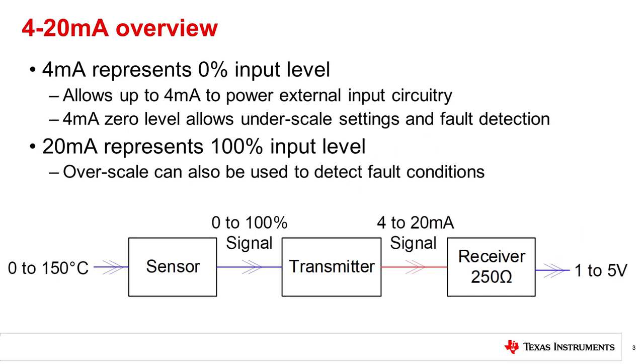The 4 to 20 milliamp current loop was designed to emulate the old 3 to 15 psi pneumatic system that was used up until the 1950s to facilitate industrial controls throughout a building. The typical 4 to 20 milliamp transmission path starts with a sensor. The sensor measures a variable over a specific range — for example, a temperature between 0 and 150 degrees C — and outputs a voltage proportional to where the measurement falls within the set range. The transmitter converts the sensor output to a 4 to 20 milliamp signal, which corresponds to the full scale of the sensor. 4 milliamps represent the minimum scale — 0 degrees C in our example — and 20 milliamps represents maximum scale — 150 degrees C. It then sends this current signal, usually over a long distance, to a receiver that converts the signal back to a voltage. A simple receiver would consist of a resistor that converts this current back to a voltage by Ohm's law. A typical value for this resistor is 250 ohms, resulting in a final voltage of 1 to 5 volts.